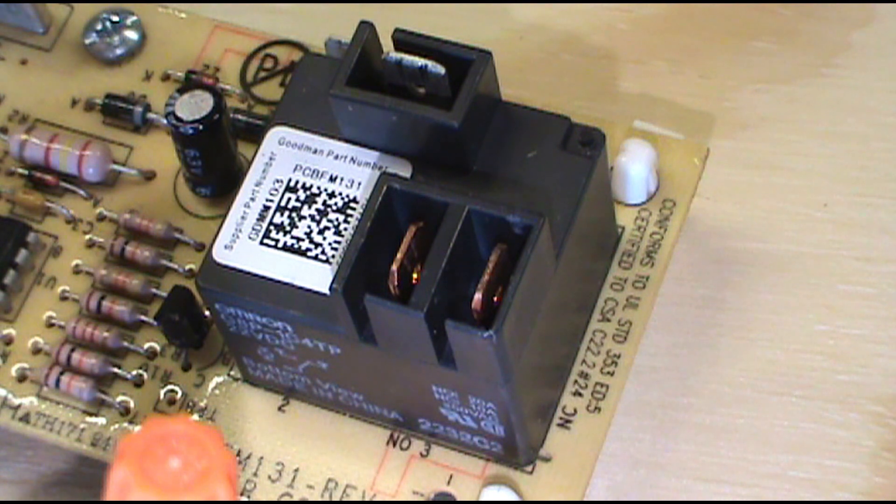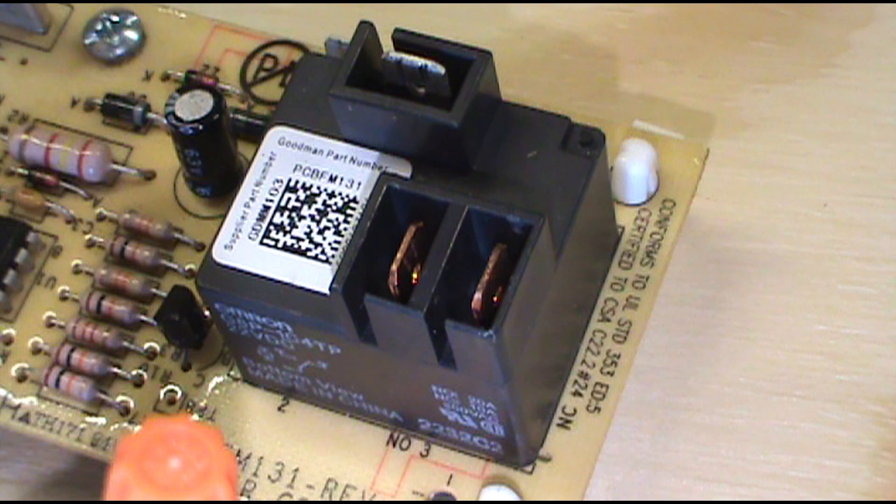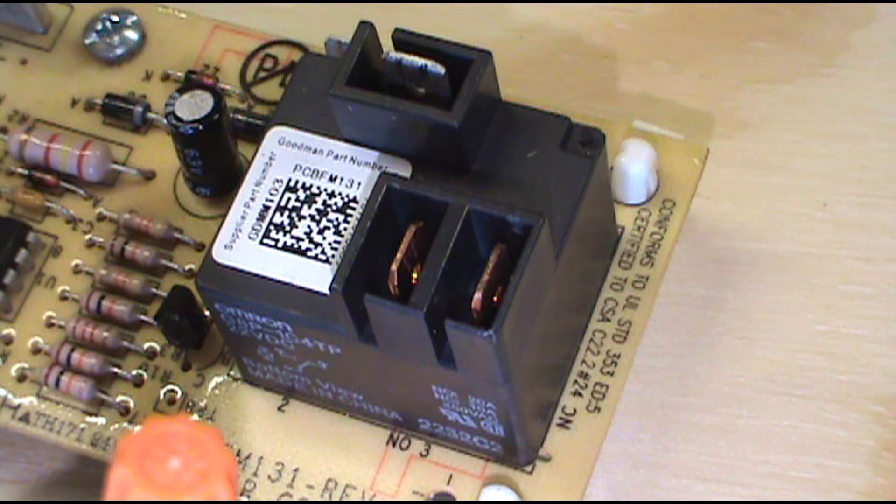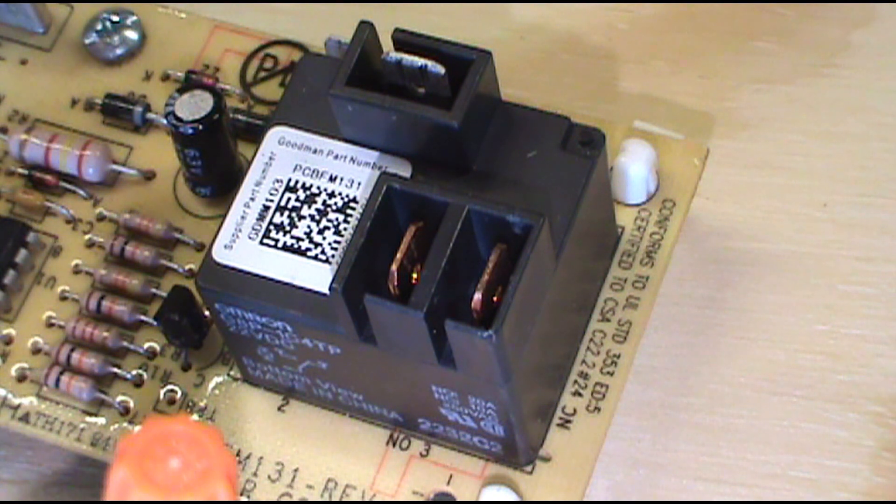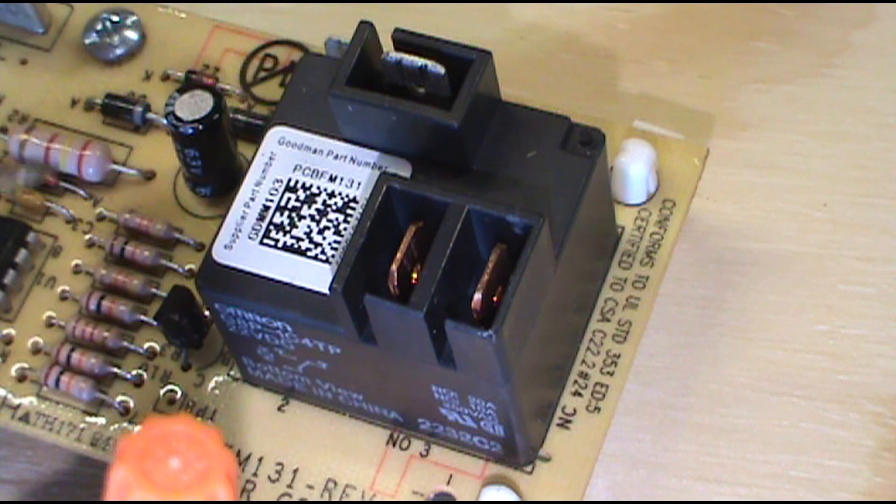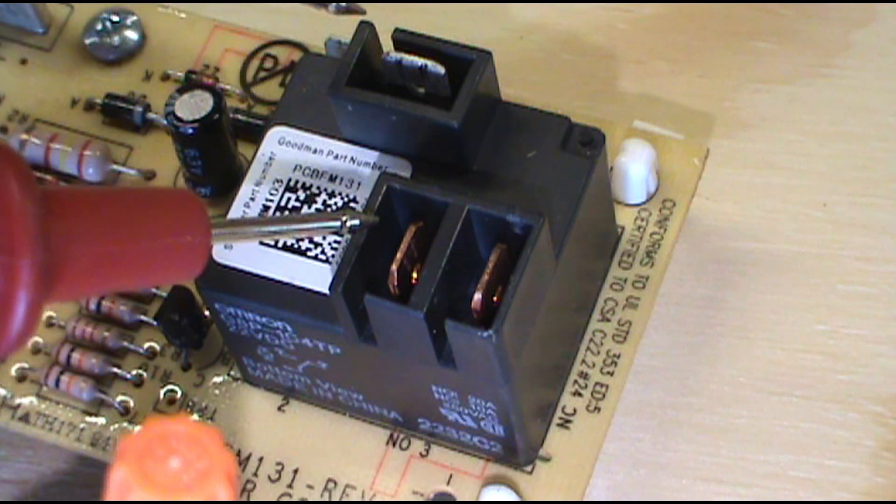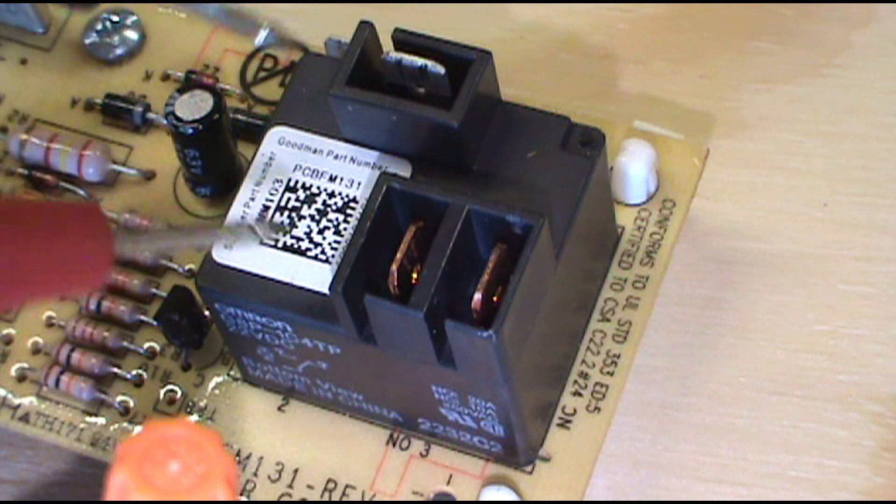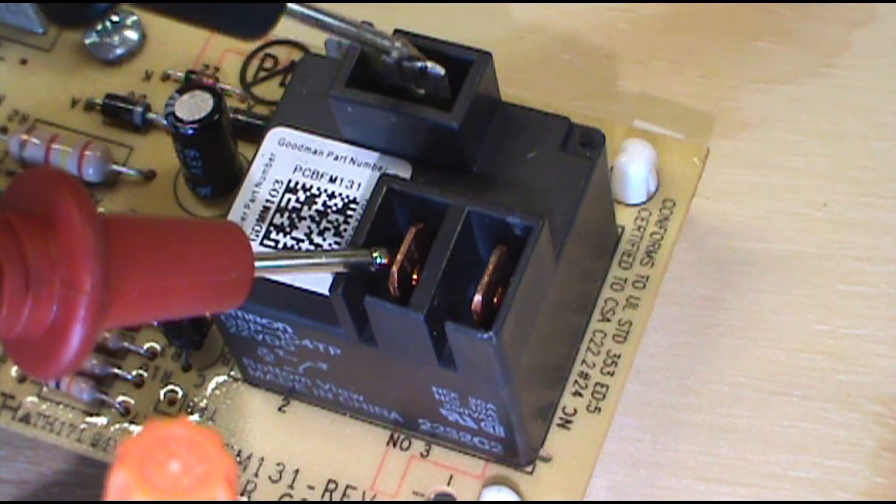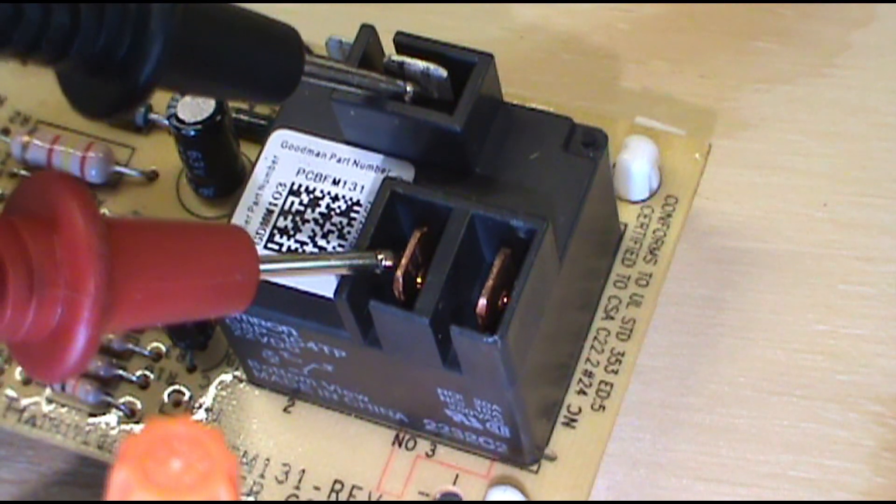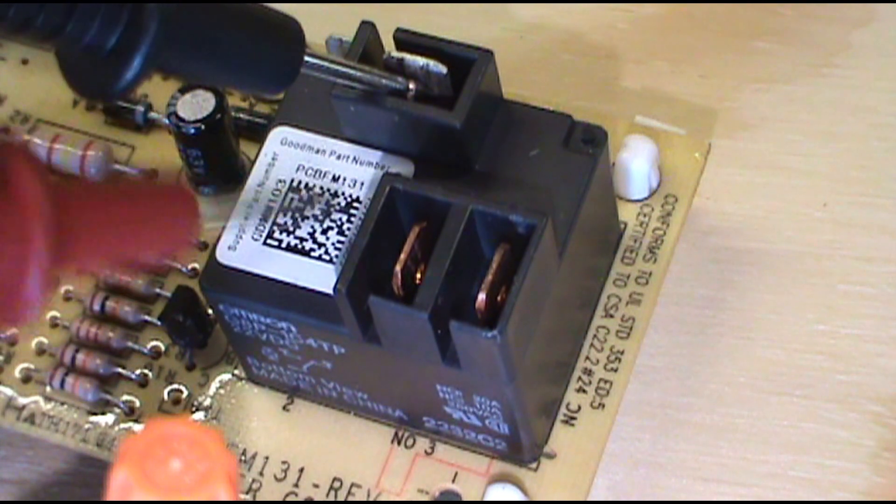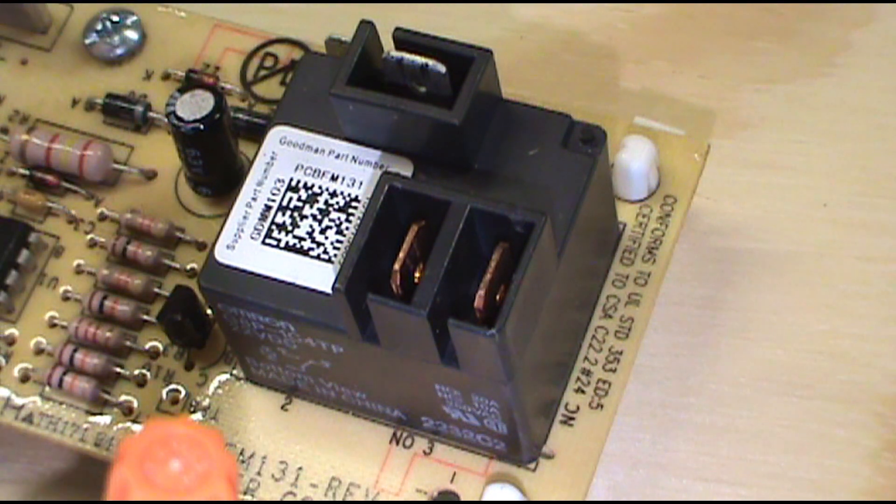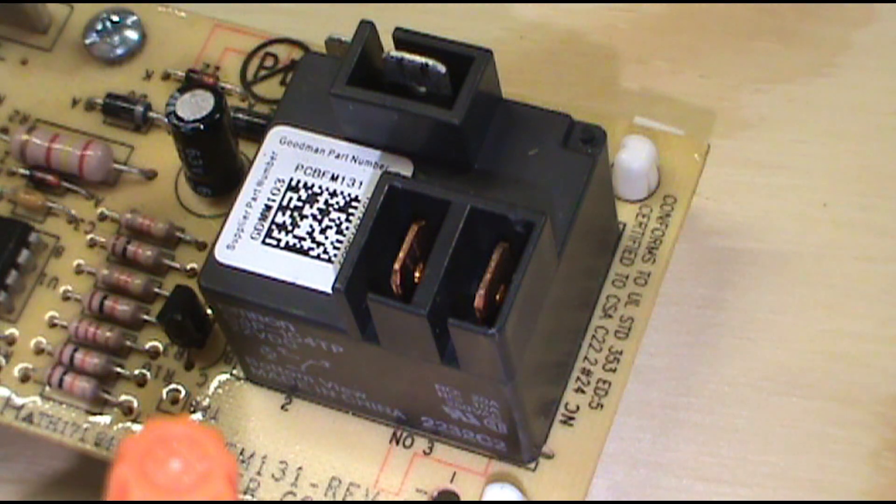Now if you got the power off, let's say somebody says hey my fan continuously runs, it never shuts off. Even when the unit is off, the fan continuously runs, never stops. What I would do is I would test, I would turn the power off, turn the breaker off and test between here and here with the power off. And if it beeps that means this is stuck closed and you have to replace it, it's bad.